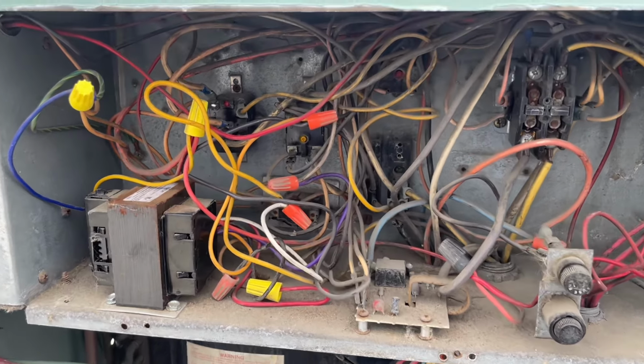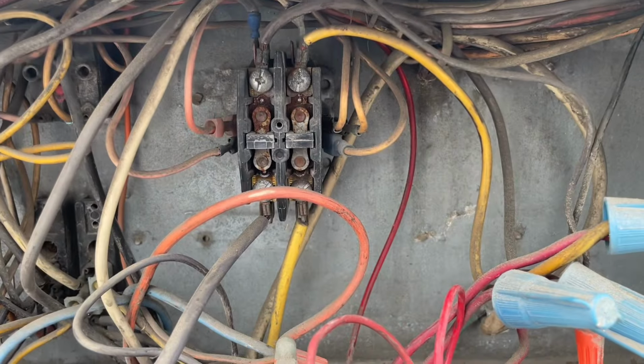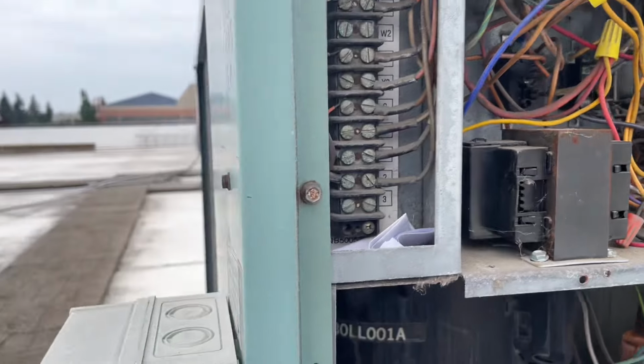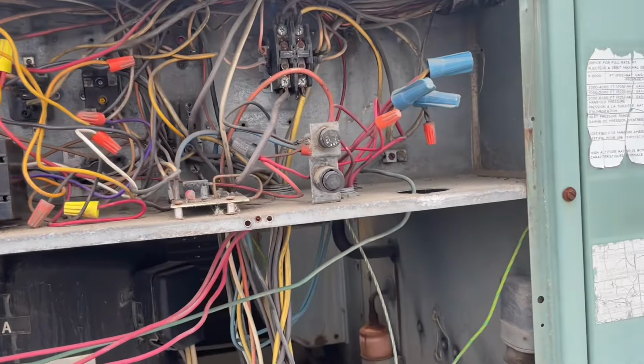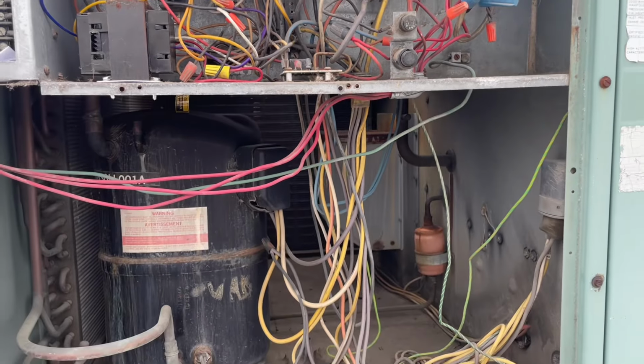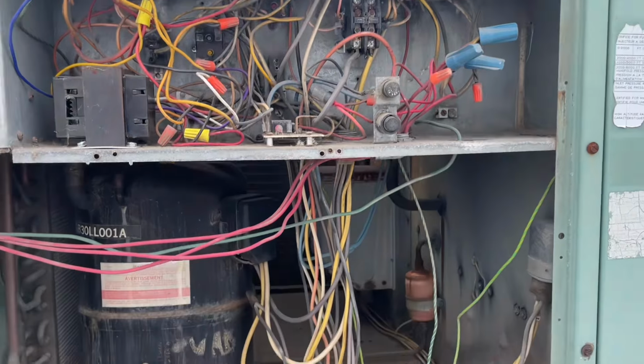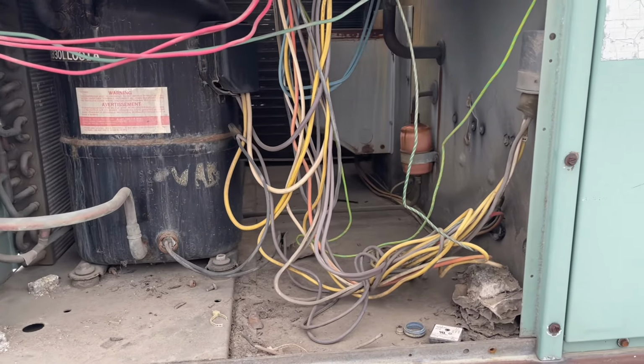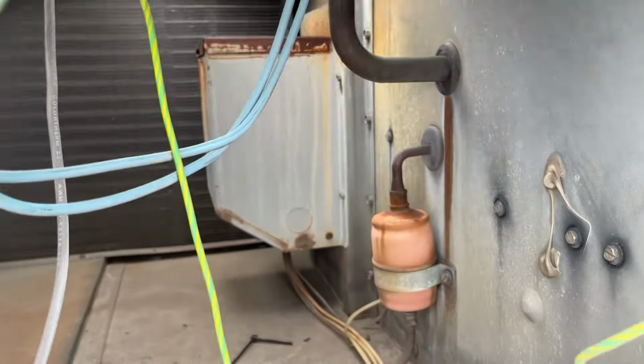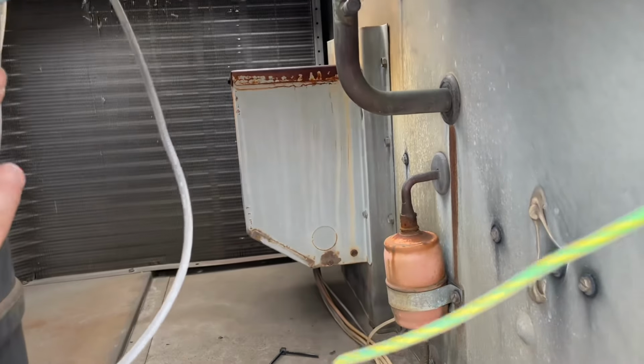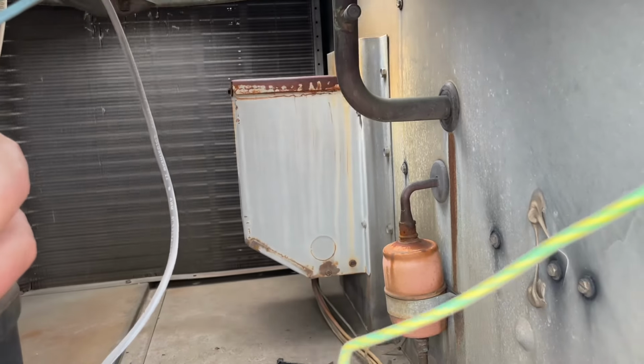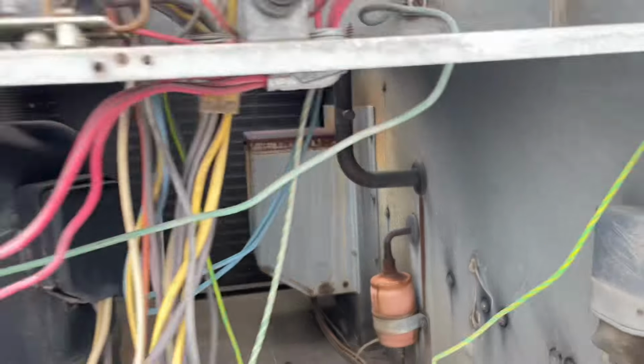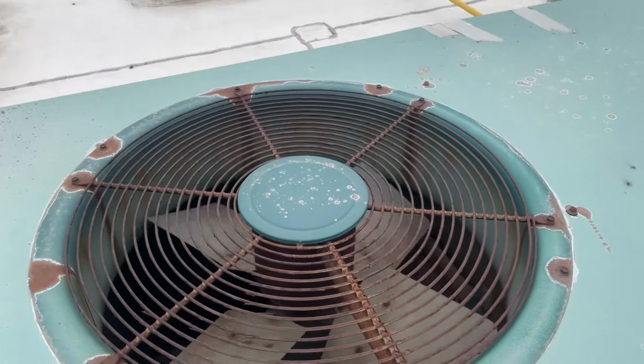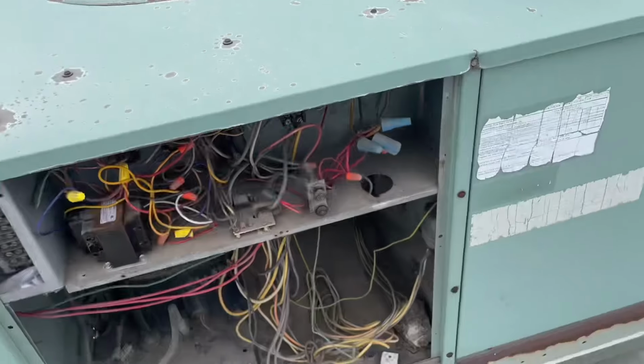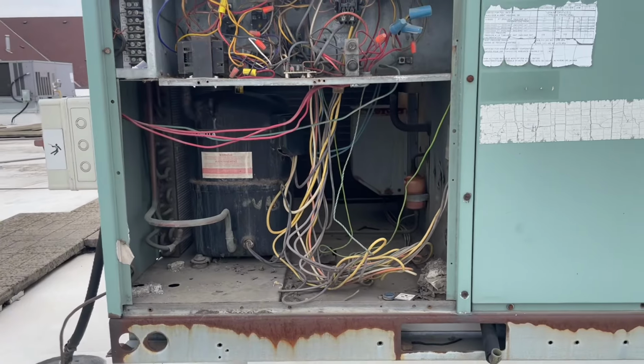Just took off the electrical cover. This puppy's in rough shape. I don't know the year of this unit, but I would guess early 90s at some point. 3 decades old at least. And there's our transformer back there. I don't know how I'm gonna get my ass in there. Might have to take that condenser fan motor off and come in from the top. I can tell you one thing, my 210-pound ass ain't fitting in that little hole.